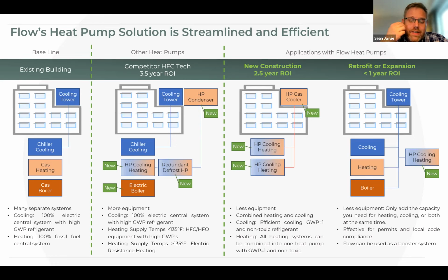Now, when you're doing a retrofit, that's a whole other story, because now let's take an existing office space with, let's say, 200 VAV units, all designed to operate at 180 degree supply water temperature. No heat pump can do that. So let's say we change the heat pumps out and they can do 120 degrees. Now at this point, you have 200 VAV boxes in a finished premium space where you've got to rip out all the walls, all the ceilings, and change 200 boxes, as well as buy all new heat pumps. And your entire building water loop needs to be upsized to account for that pressure difference and the temperature difference. That is a very expensive proposition.